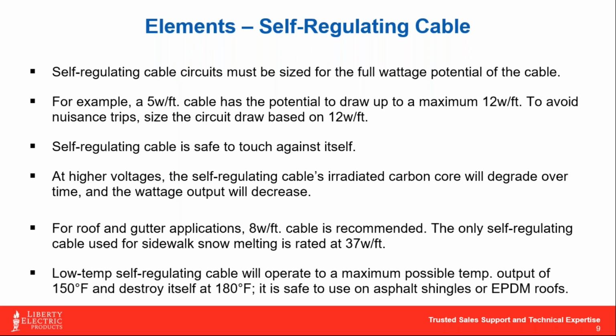So again, if you've got a 208 volt facility and we're using a cable designed around 240 volt and we're expecting 8 watts a foot, we're really only going to get 7. But if that voltage is really down around 202 or 200, you're going to get even less. So these are the things that, again, we look for on the front side.